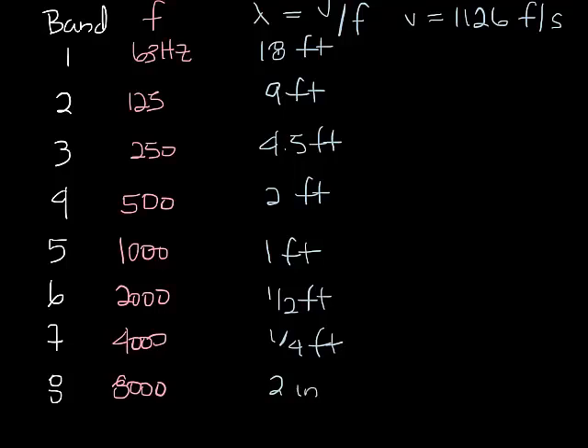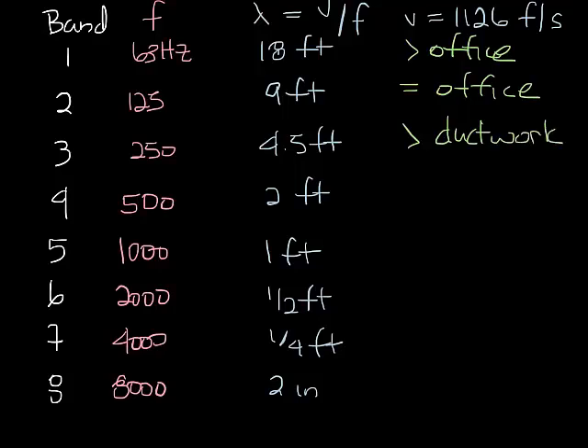Now if you visualize a sound wave, now that you know how long they are, you can quickly see how some sound waves, low-frequency waves in particular, are too large to be absorbed by normal construction materials. For instance, the first band wave is 18 feet. That's larger than the average office. The second one is 9 feet, about the size of an office. The third band is 4 1⁄2 feet. That's larger than most duct work. The fourth band is 2 feet. That's probably about the size of most duct work.